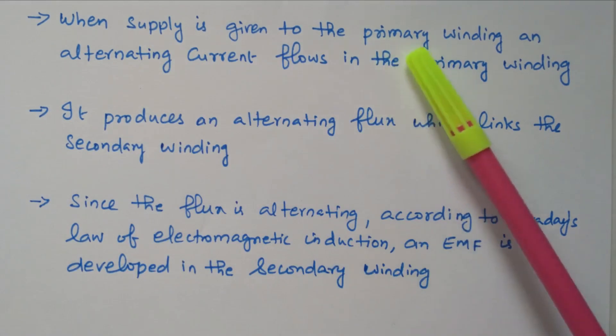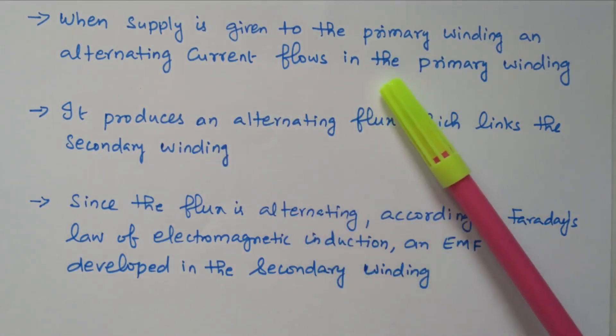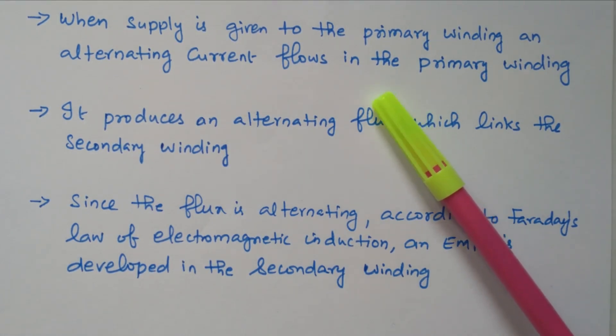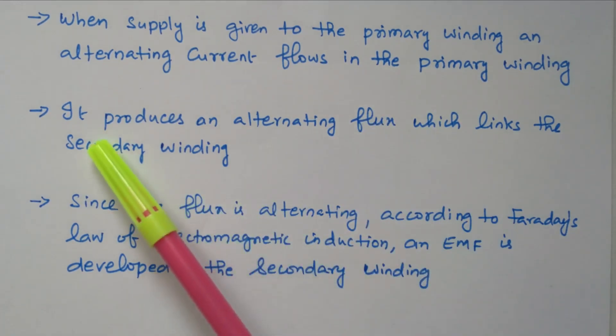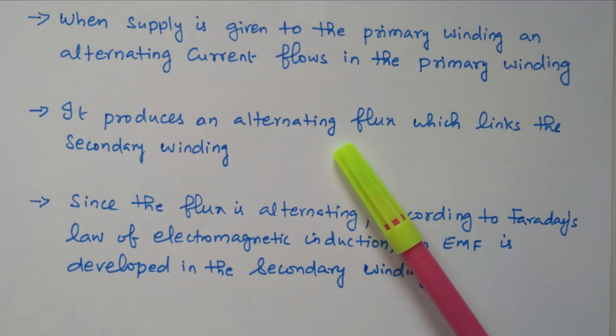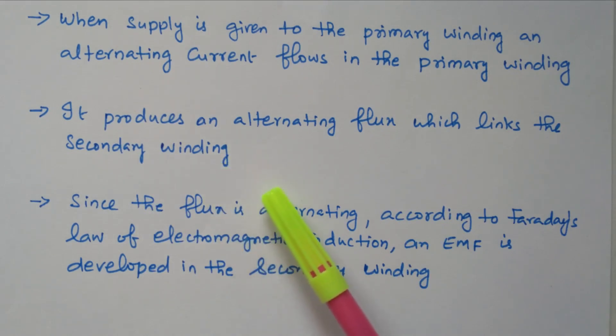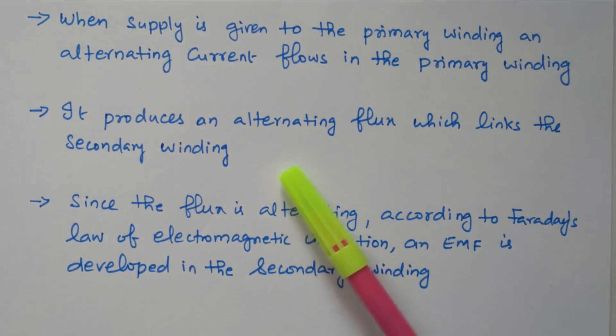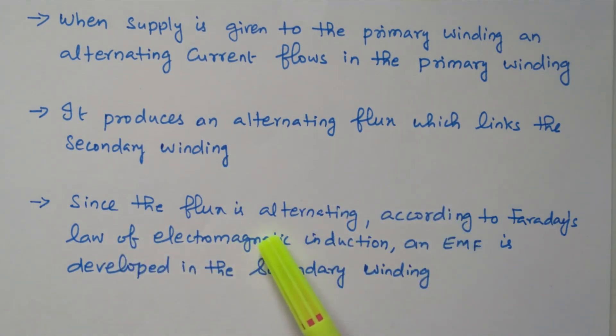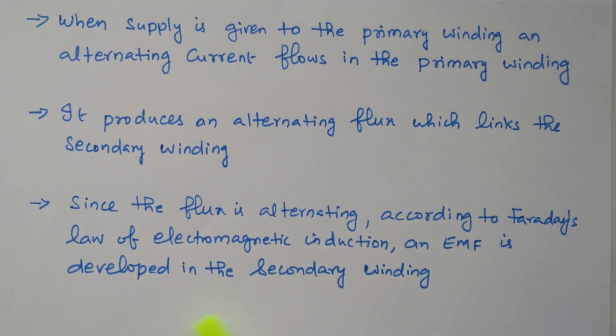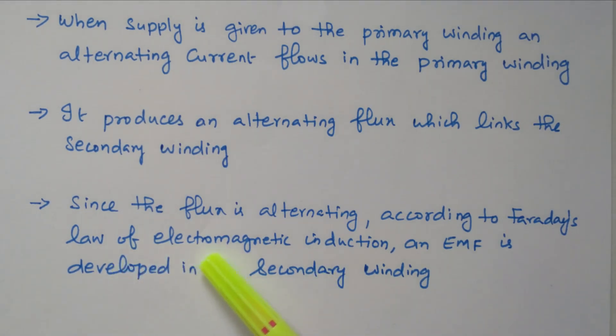When supply is given to the primary winding, an alternating current flows in it, producing alternating flux. This flux links with the secondary winding through the iron core. Since the flux is alternating, according to Faraday's law of electromagnetic induction, an EMF is induced in the secondary winding. Due to the rate of change of flux, the EMF is induced in the secondary winding — this is the basic principle of the transformer.